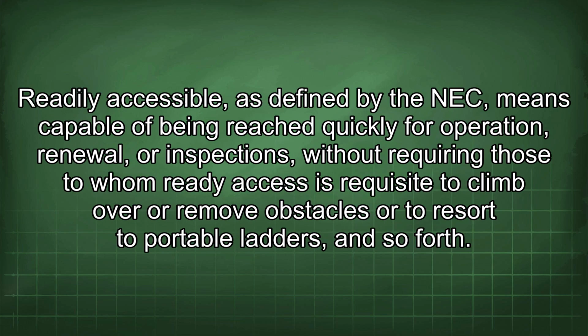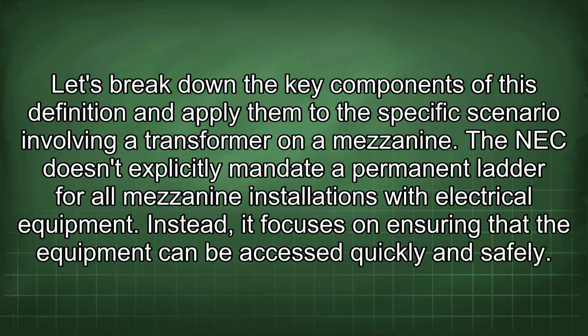Readily accessible, as defined by the NEC, means capable of being reached quickly for operation, renewal, or inspection, without requiring those to whom ready access is requisite to climb over or remove obstacles or to resort to portable ladders, and so forth. Let's break down the key components of this definition and apply them to the specific scenario involving a transformer on a mezzanine.